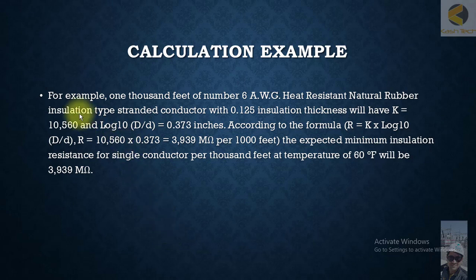Let's calculate now minimum required insulation resistance. For example, 1000 feet of number 6 AWG heat resistant natural rubber insulation type stranded conductor with 0.125 insulation thickness will have K equal to 10,560.